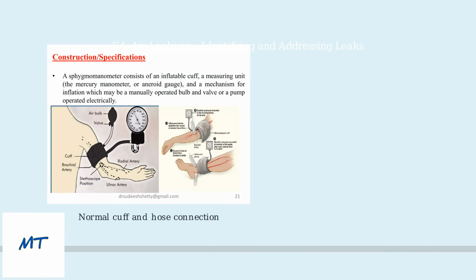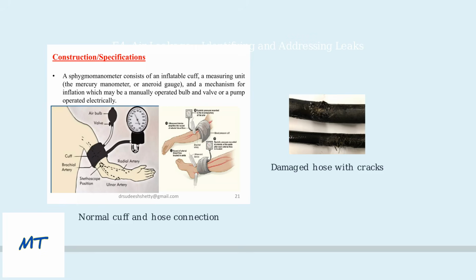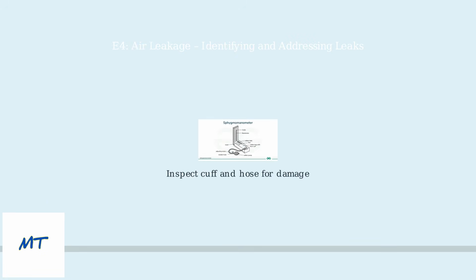E4 indicates air escaping from the cuff or hose, preventing accurate blood pressure readings. In a properly functioning system, the cuff and hose form a sealed connection that maintains pressure during measurement. E4 errors are typically caused by a worn-out cuff, cracks in the hose, or improper inflation that allows air to escape. To address E4, inspect the cuff and hose for visible damage like cracks or wear. Replace any worn or damaged components to restore the sealed system. Always ensure the cuff is properly sealed during inflation to maintain the necessary pressure for accurate readings.